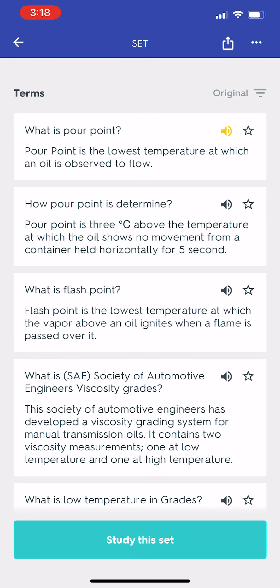What is pour point? Pour point is the lowest temperature at which an oil is observed to flow. How is pour point determined? Pour point is 3°C above the temperature at which the oil shows no movement from a container held horizontally for 5 seconds. What is flash point? Flash point is the lowest temperature at which the vapor above an oil ignites when a flame is passed over it.